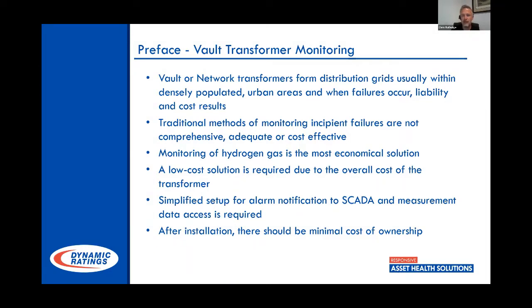However, with these failures, especially ones related to cable compartments of this transformer, anytime you have a catastrophic failure, there's quite a bit of liability and cost as a result of that. I've actually seen customers injured as a result of these. We've seen building fires, a lot of damage associated, and then of course negative media that goes with that. So when I got to really looking at these and trying to figure out, okay, how do I prevent that? I went to all the vendors out there on the market, and you were running into the price point of the equipment, because the transformers are not terribly expensive in relation to, say, a substation transformer where you're spending $2 or $3 million.